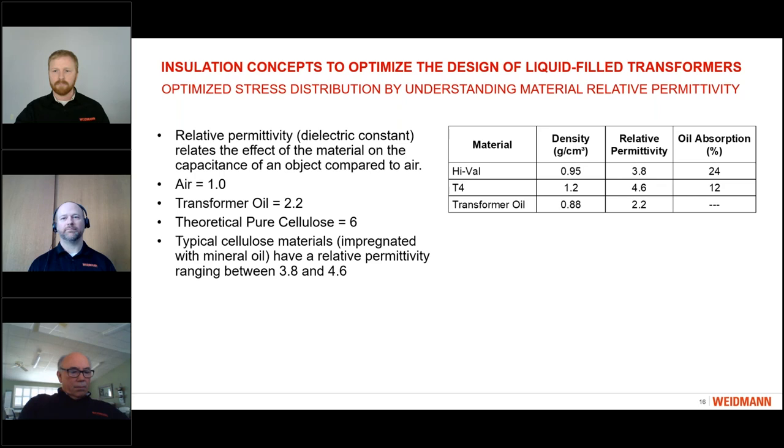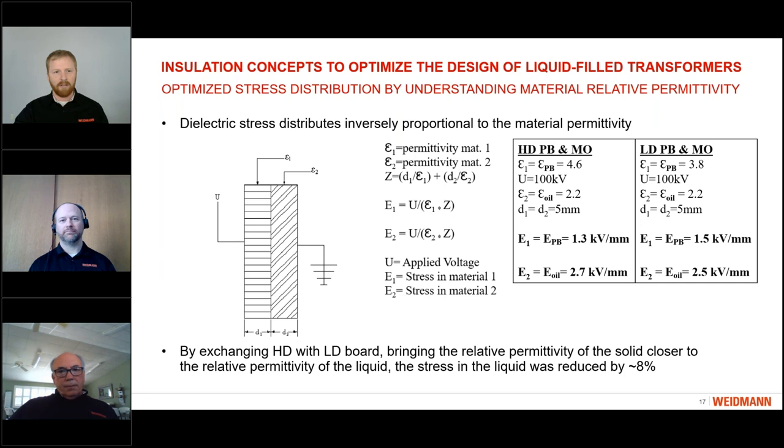So when we look at how the relative permittivity of the solid material dictates stress, we first need to understand that dielectric stress distributes inversely proportional to the relative permittivity. Showing here the calculation method for understanding that, and I don't want to go into a lot of detail on that, but really just understand that the stress distributes inversely proportional.